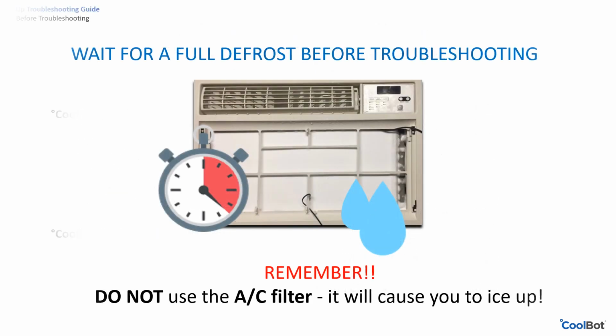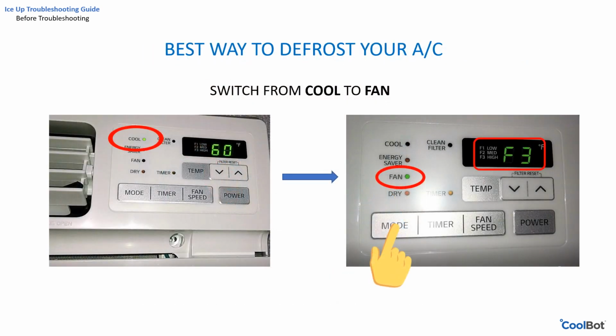It is very important that all ice is completely melted in order to troubleshoot your system. In order to do this, turn your air conditioner to the fan-only mode to allow it to defrost. This is the fastest way to defrost your air conditioner. This is better than unplugging your air conditioner from the wall, and it will allow us to know from the beginning if there is a problem with the air conditioner.